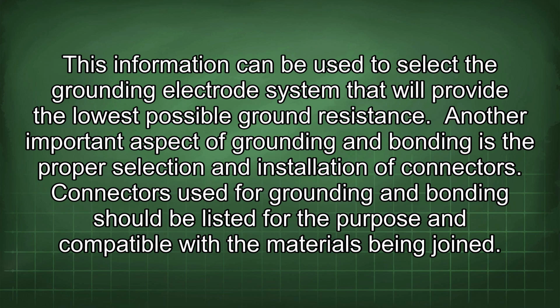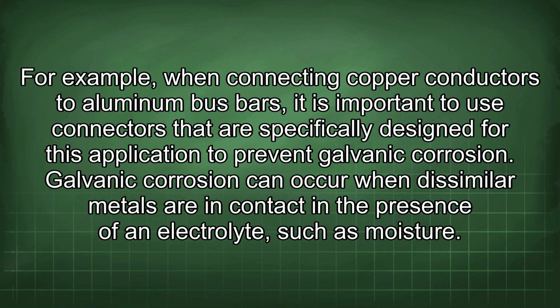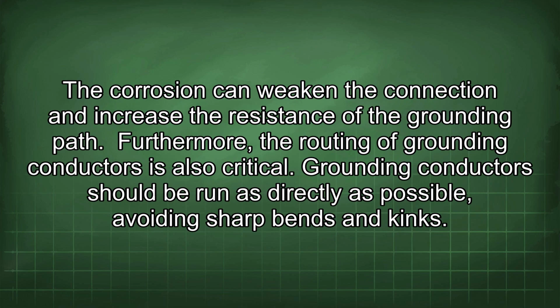Another important aspect of grounding and bonding is the proper selection and installation of connectors. Connectors used for grounding and bonding should be listed for the purpose and compatible with the materials being joined. For example, when connecting copper conductors to aluminum bus bars, it is important to use connectors that are specifically designed for this application to prevent galvanic corrosion. Galvanic corrosion can occur when dissimilar metals are in contact in the presence of an electrolyte such as moisture. The corrosion can weaken the connection and increase the resistance of the grounding path.